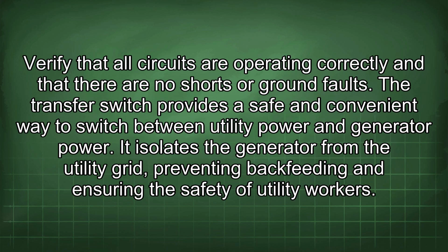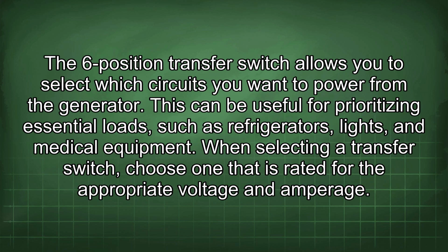Verify that all circuits are operating correctly and that there are no shorts or ground faults. The transfer switch provides a safe and convenient way to switch between utility power and generator power. It isolates the generator from the utility grid, preventing backfeeding and ensuring the safety of utility workers. The 6-position transfer switch allows you to select which circuits you want to power from the generator. This can be useful for prioritizing essential loads such as refrigerators, lights, and medical equipment.